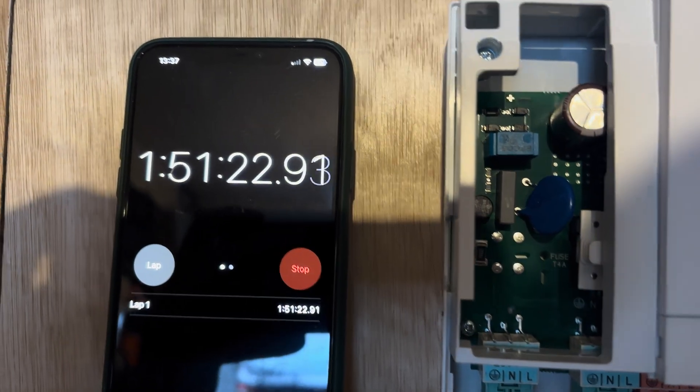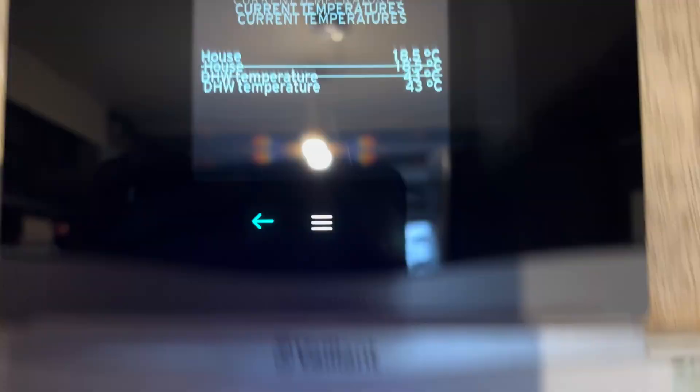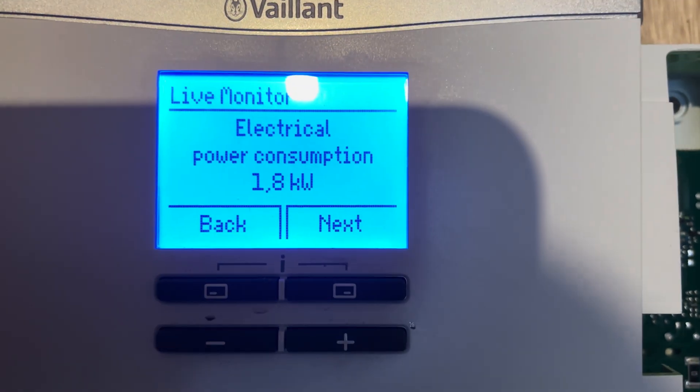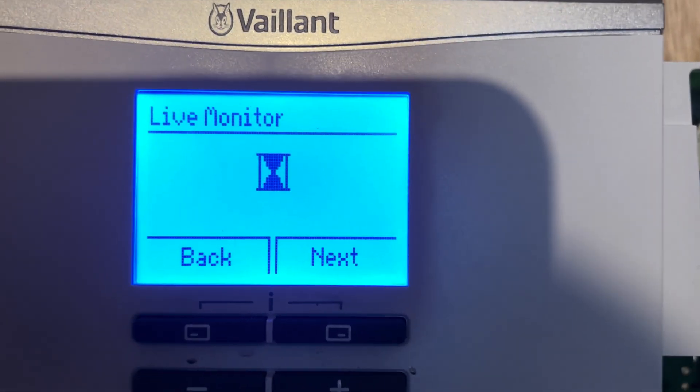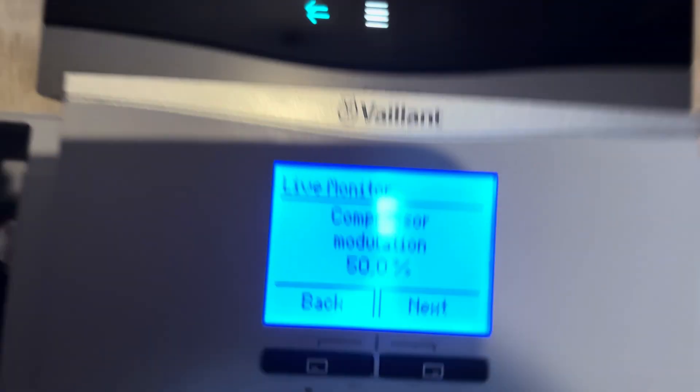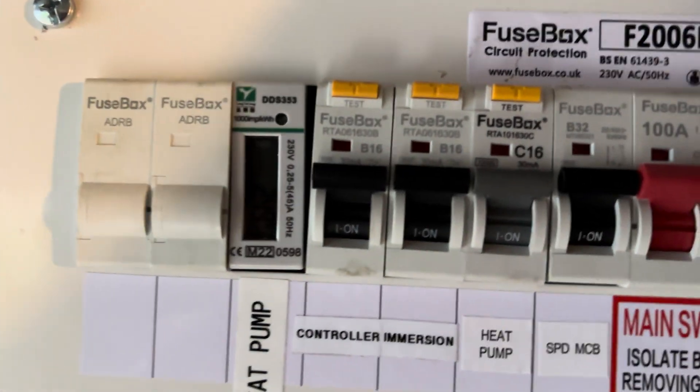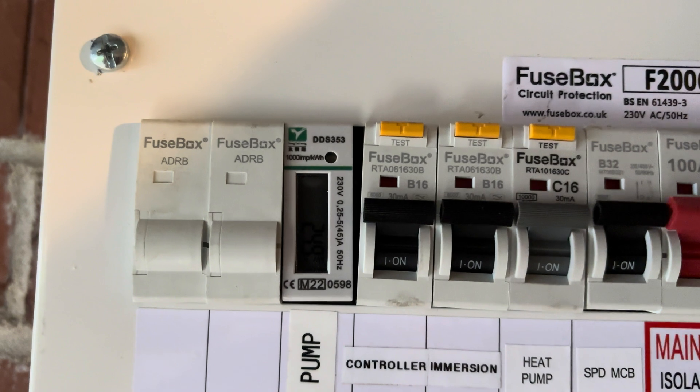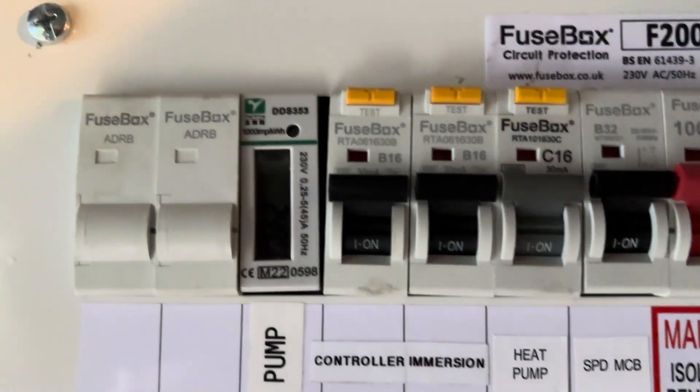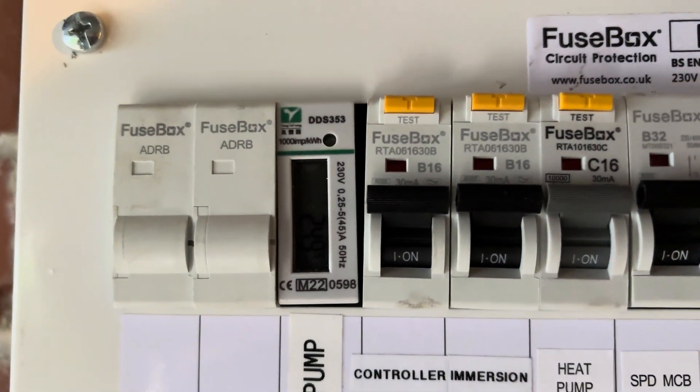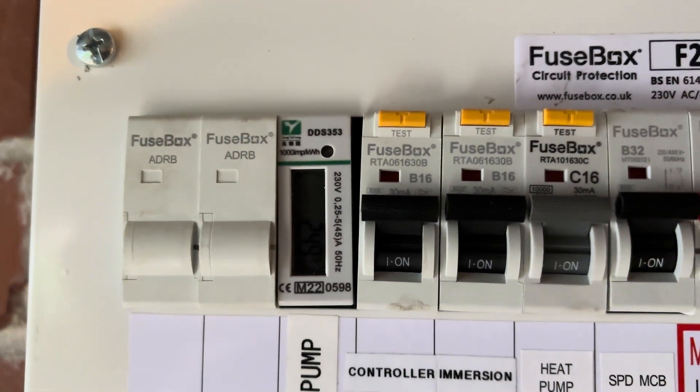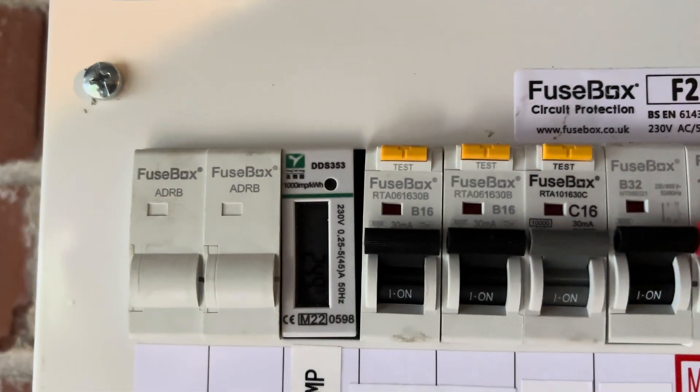Just over 1 hour 50 minutes. 43 degrees C. Power consumption is now all the way up to 1.8. Modulation 50%. And we've used 2.48 kilowatts of electric so far to get from 11 degrees C to 43.